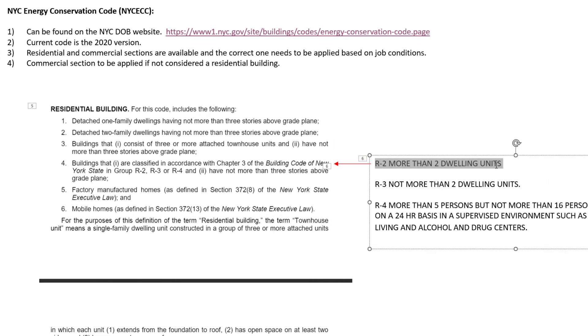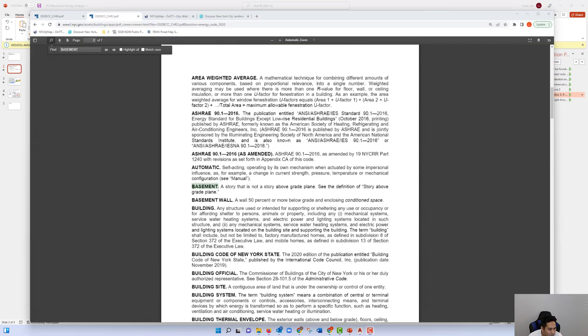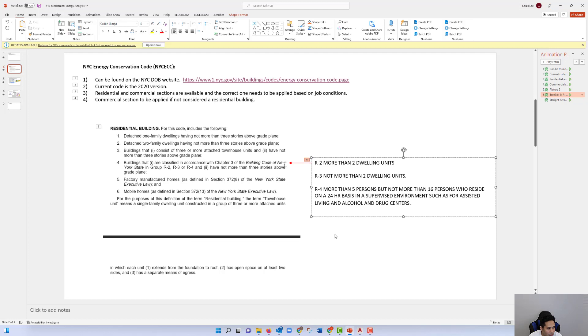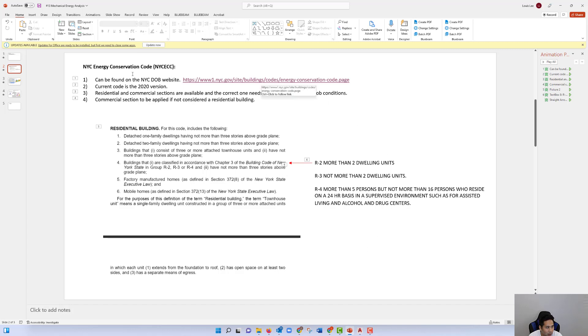Going back to the definitions, a three-family unit falls under R2 — more than two family units. For R2, it cannot have more than three stories above grade plane. In the energy code, a basement is defined as a story that is not a story above grade plane, so it doesn't count. With floors one, two, and three, we have not more than three stories above grade plane, so the NYC residential energy code applies.